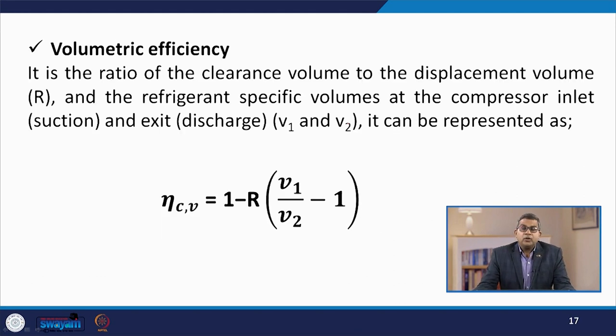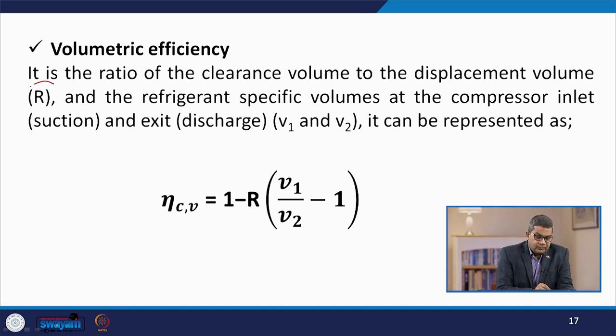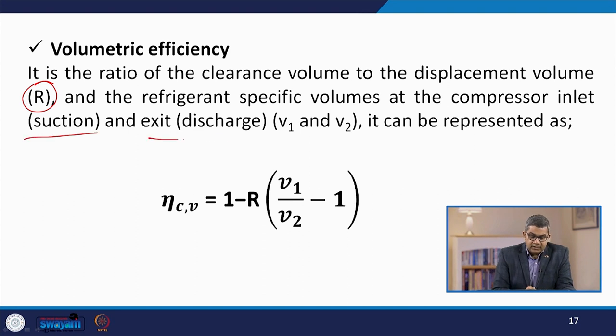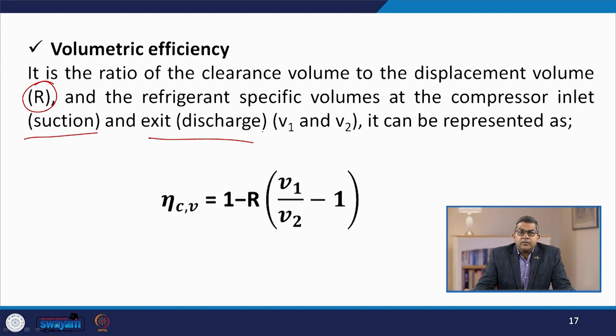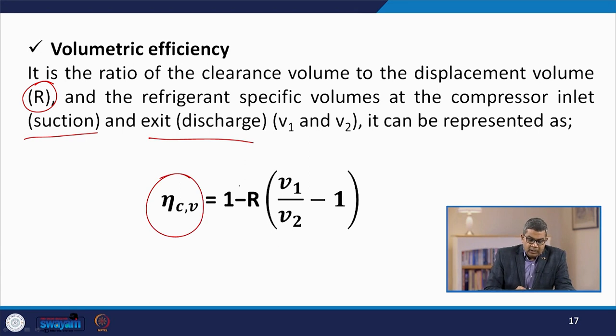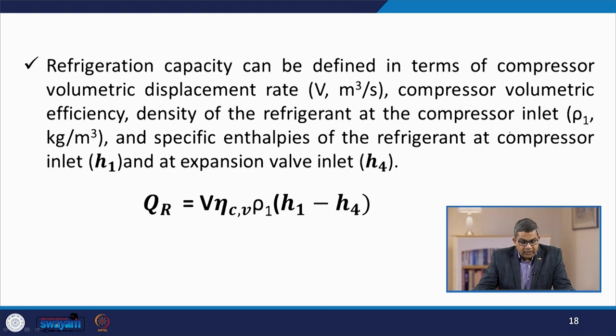Volumetric efficiency is the ratio of clearance volume to displacement volume r, and the refrigerant specific volumes at compressor inlet (suction) v₁ and exit (discharge) v₂. Mathematically, volumetric efficiency η_v = 1 − r × (v₁/v₂ − 1).